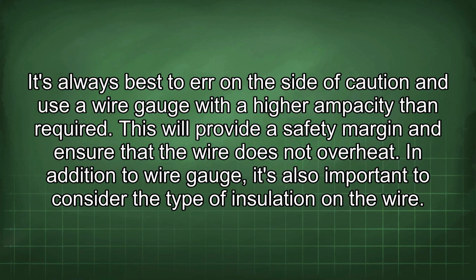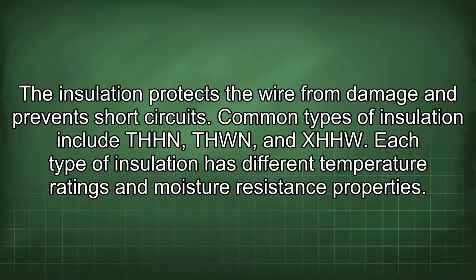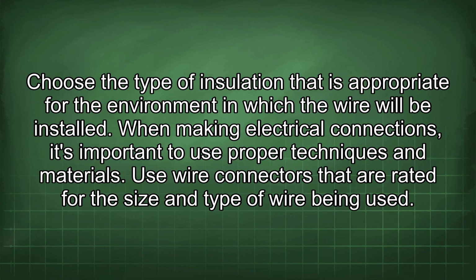In addition to wire gauge, it's also important to consider the type of insulation on the wire. The insulation protects the wire from damage and prevents short circuits. Common types of insulation include THHN, THWN, and XHHW. Each type of insulation has different temperature ratings and moisture resistance properties. Choose the type of insulation that is appropriate for the environment in which the wire will be installed.